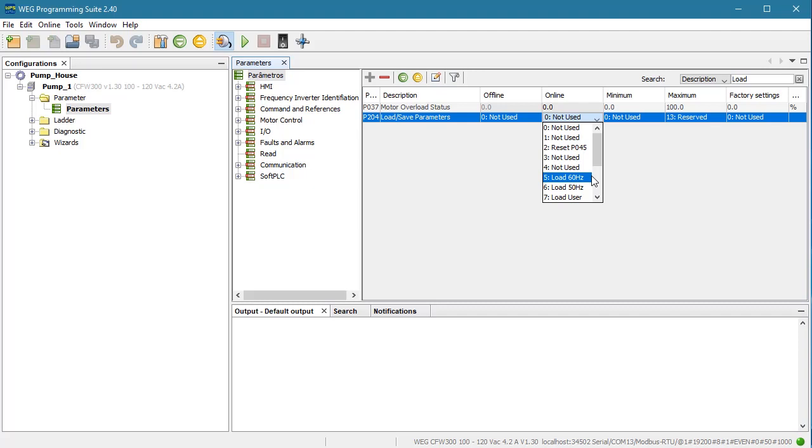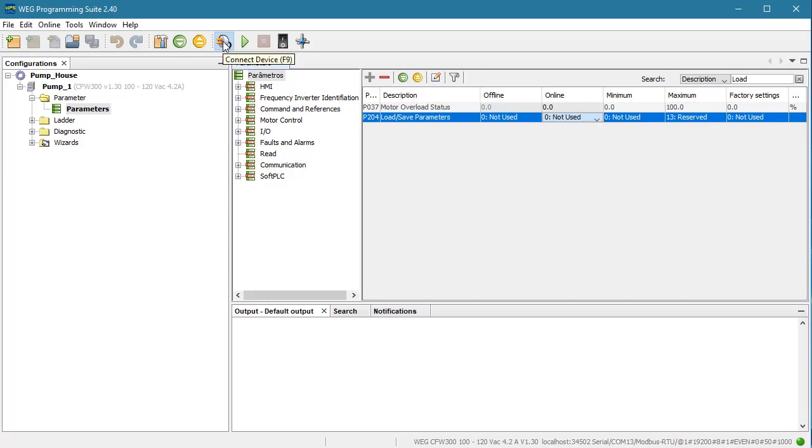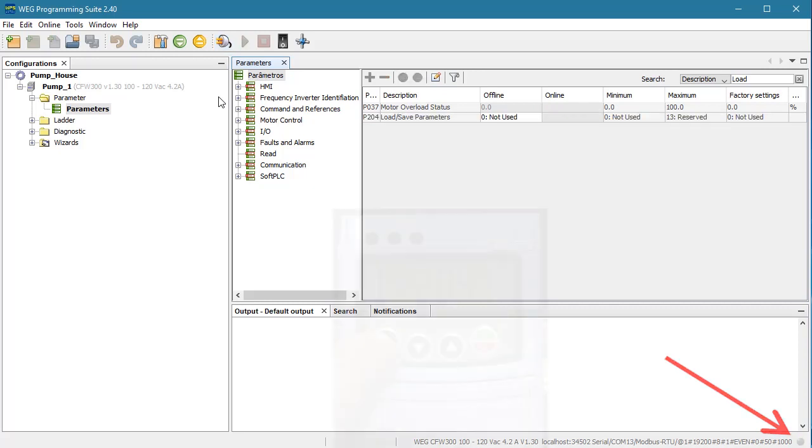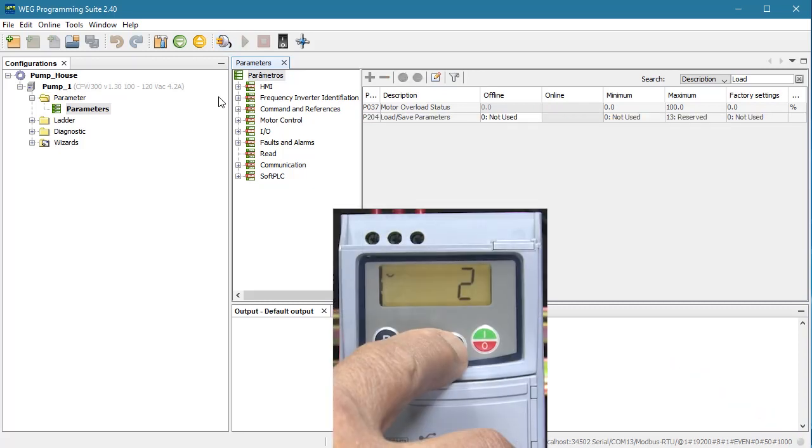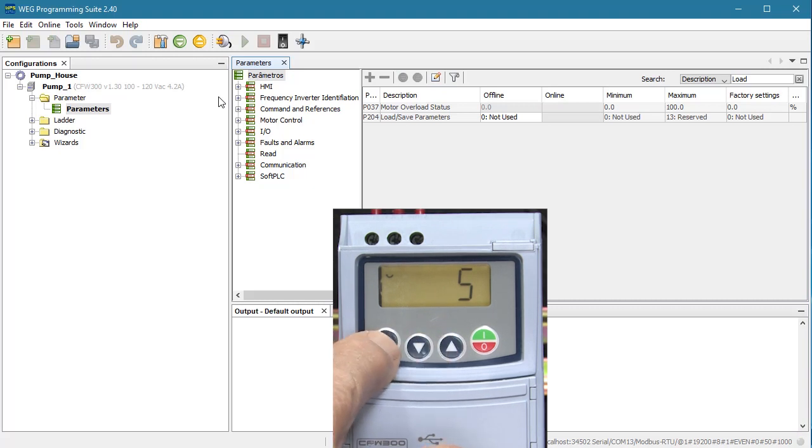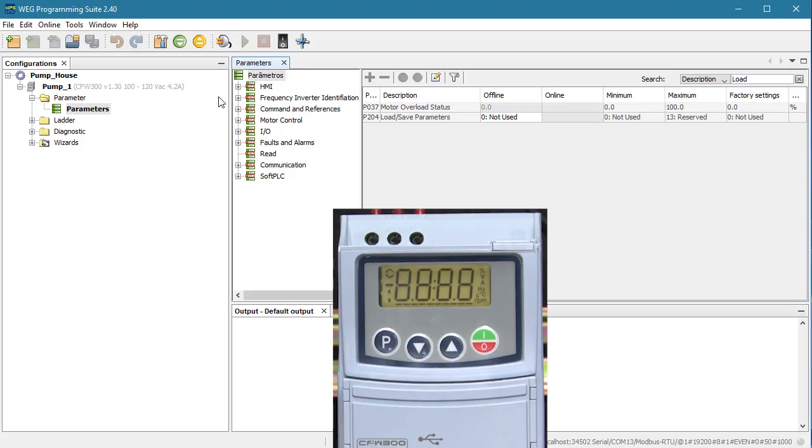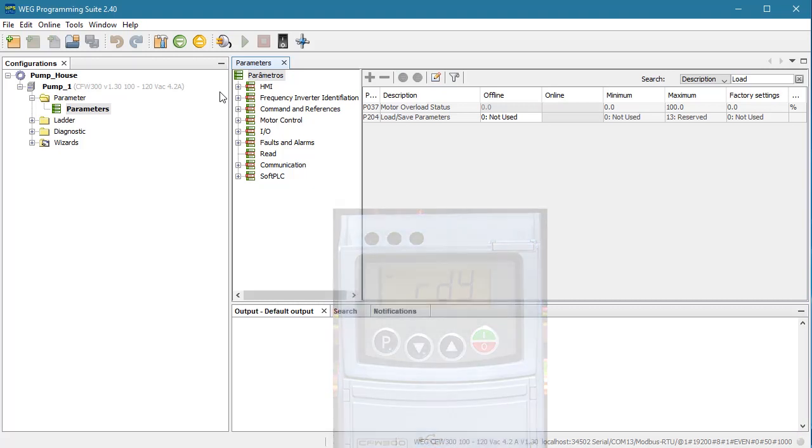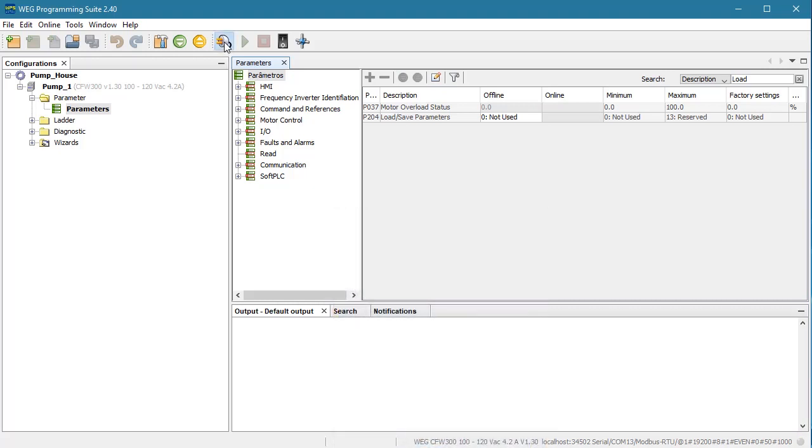If you are using WPS, then be sure to disconnect WPS from the drive to get a clean exit. That can take several seconds while WPS finalizes everything for a clean disconnect, so be patient. Keep an eye on this little green connection indicator down here. When it turns gray, you know WPS is fully disconnected from the drive. When that's done, then you can do a drive reset from the drive's keypad, and when that's done, you can reconnect WPS.